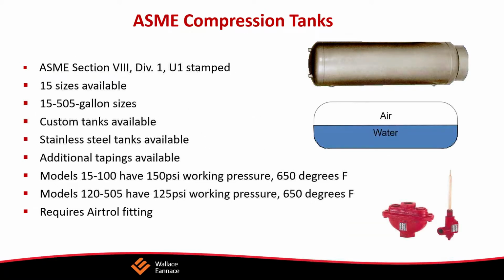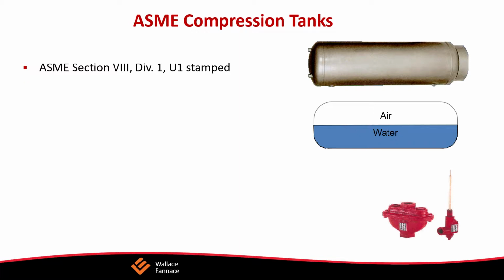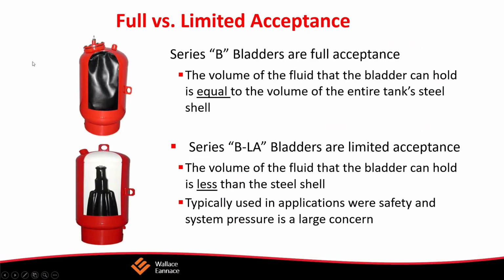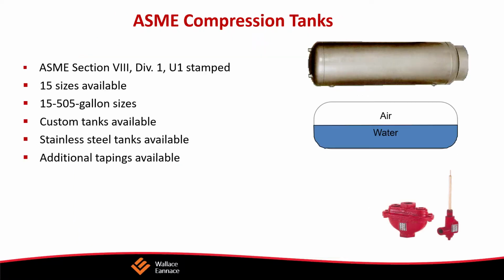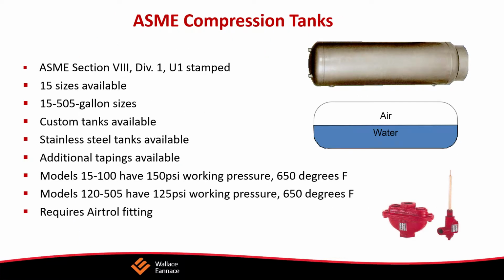So the air and water pressures must match before the system is filled. Before you connect it to the system, you need to set the pressure inside the tank on the air side. That's critical. There's a Schrader valve on the bottom, and that's where you set the pressure before you install the expansion tank.